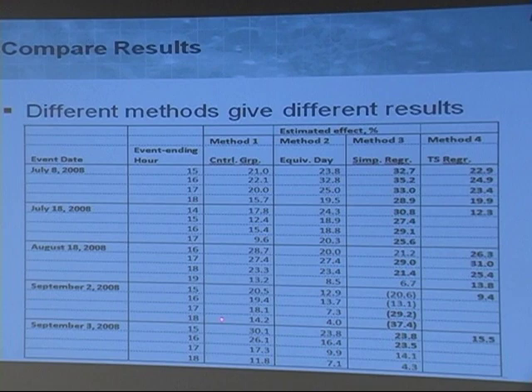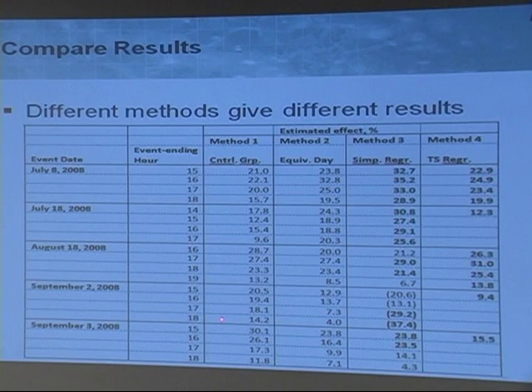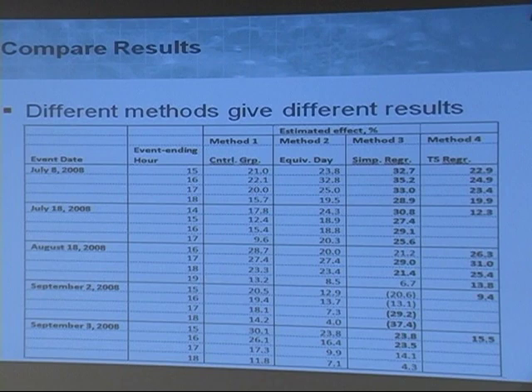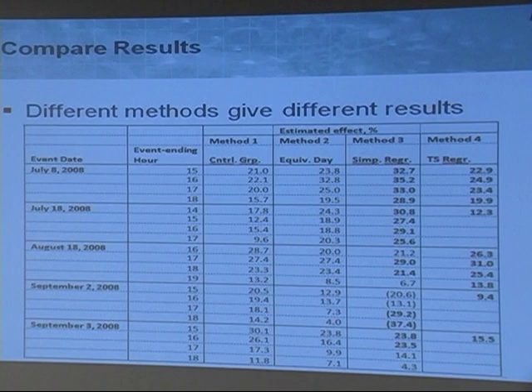We applied all four methods to this dataset and got four different answers. These are the five event days with their event hours — which vary slightly depending on when each event started and which four-hour period it covered. These are the four methods I described, and the numbers show the percentage reduction in power estimated by each. One obvious trend is that the effect size is typically larger earlier in the event than later, which is what you'd expect.